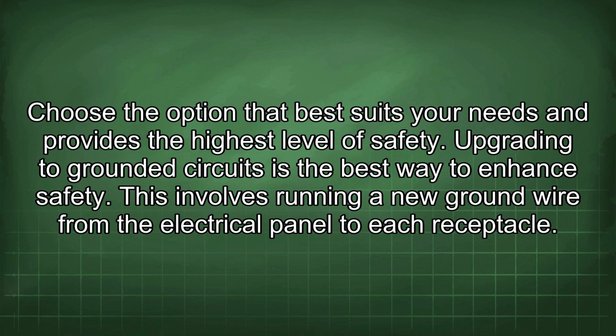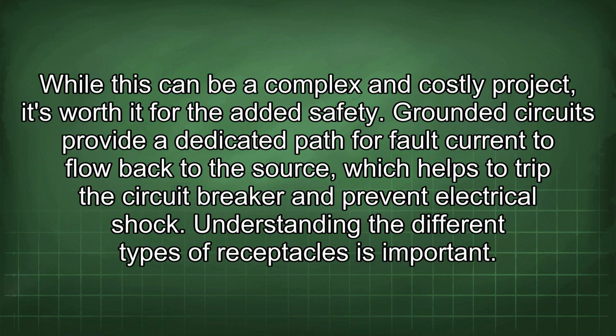Upgrading to grounded circuits is the best way to enhance safety. This involves running a new ground wire from the electrical panel to each receptacle. While this can be a complex and costly project, it's worth it for the added safety. Grounded circuits provide a dedicated path for fault current to flow back to the source, which helps to trip the circuit breaker and prevent electrical shock.